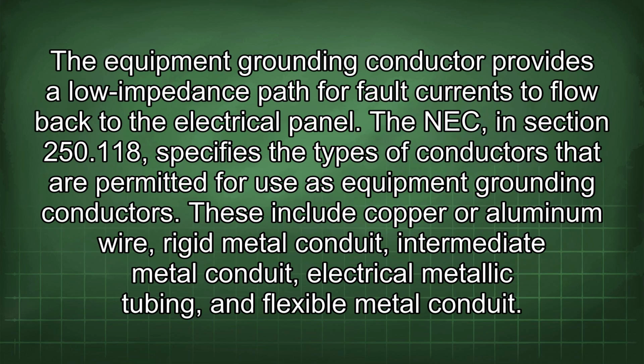The equipment grounding conductor provides a low impedance path for fault currents to flow back to the electrical panel. The NEC in section 250.118 specifies the types of conductors that are permitted for use as equipment grounding conductors. These include copper or aluminum wire, rigid metal conduit, intermediate metal conduit, electrical metallic tubing, and flexible metal conduit.